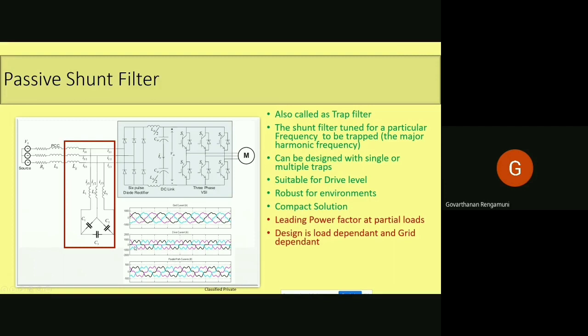You can see the drive side current. It is a pulsated one as shown here. But after adding the filter, you can see the grid current became sinusoidal. The first waveform shows close to sinusoidal current at the grid side. It is a compact solution and robust for environments because there is no active components involved here.